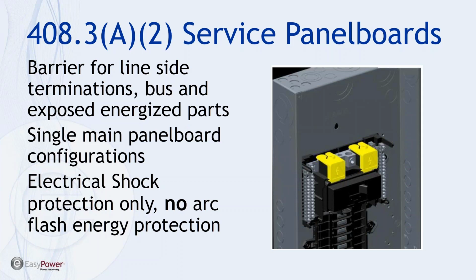And frequently this is an area that's not well understood. We're not too worried about the main breaker not working unless we have doubts about how well it's been maintained. The issue is, if an arc initiates in the panel, will the potential plasma ball engulf the main and sustain the arc in spite of the main breaker tripping?